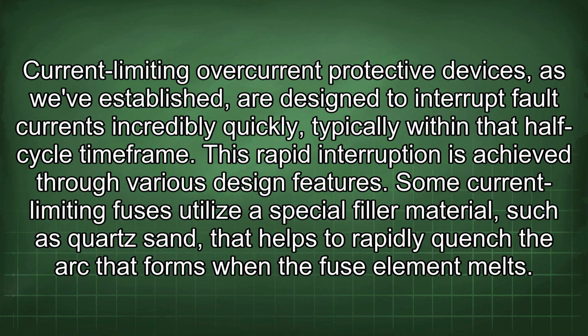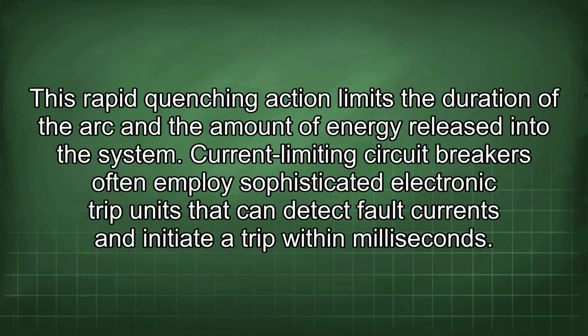Current-limiting overcurrent protective devices, as we've established, are designed to interrupt fault currents incredibly quickly, typically within that half-cycle time frame. This rapid interruption is achieved through various design features. Some current-limiting fuses utilize a special filler material, such as quartz sand, that helps to rapidly quench the arc that forms when the fuse element melts. This rapid quenching action limits the duration of the arc and the amount of energy released into the system.